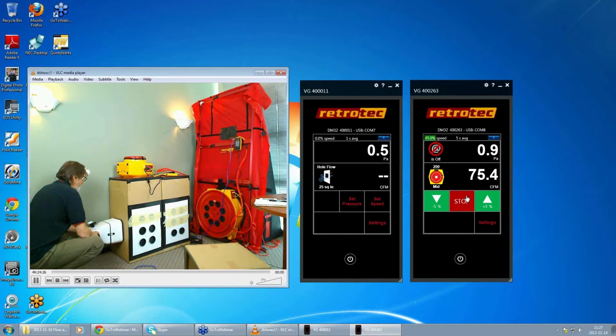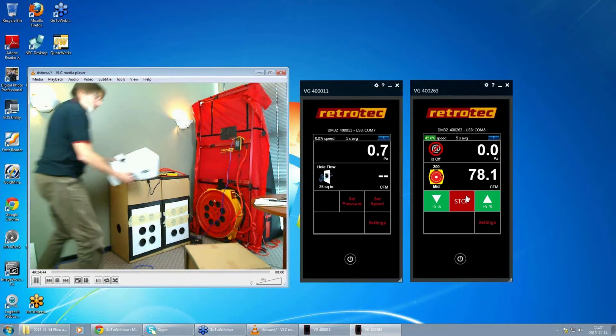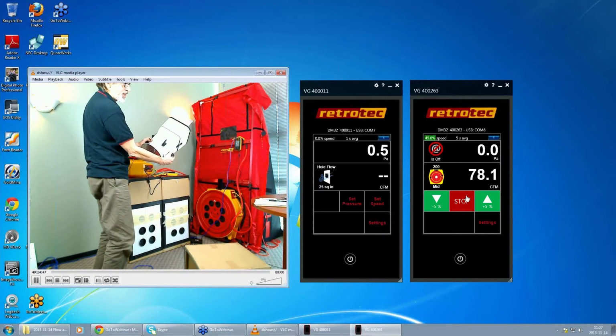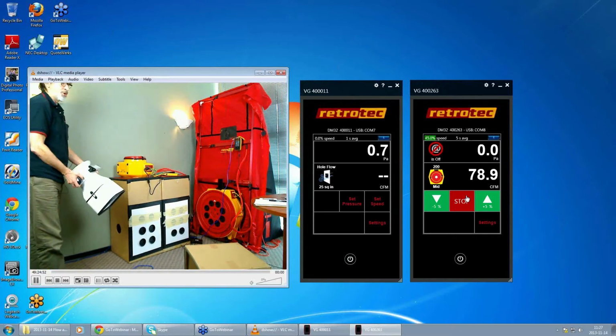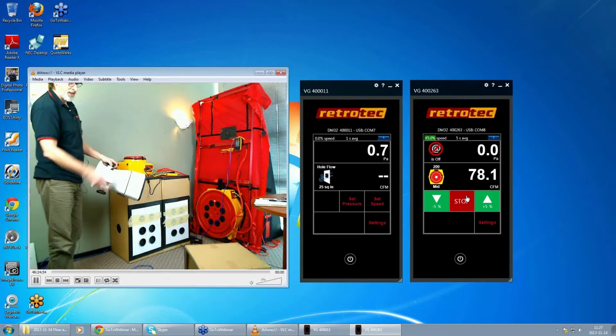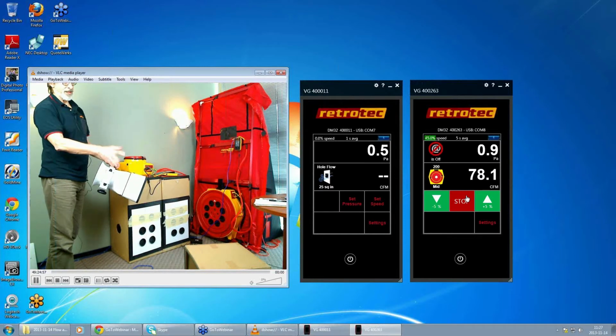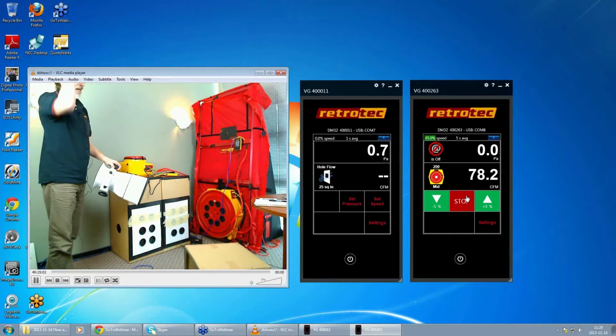So first of all, we mount it on here. We press the go button, and it's compensating the pressure. It's bringing the pressure down to 0. And I don't know if you can see that, but that says 77.5 CFM. So you can see the huge amount of accuracy difference that we have between this box, which worked perfectly well under depressurization, worked really, really poorly under pressurization. The Flow Finder managed to get a result that's within 1% or 2.